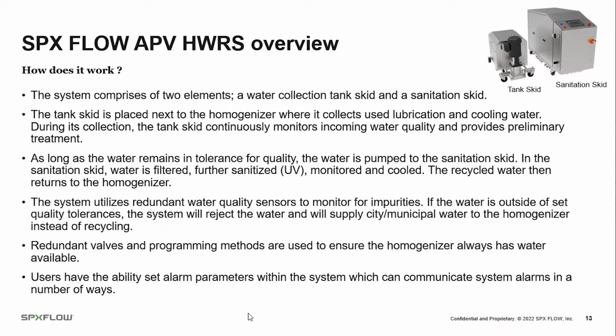The system uses redundant water quality sensors to monitor for impurities. So in the tank skid, for example, we're monitoring dissolved solids, conductivity, and temperature. And when the water is outside of set tolerances, the system will reject it and then will continually supply the city or municipal water to the homogenizer instead of recycling. The redundant valves and programming methods are used to ensure that the homogenizer water supply is uninterrupted.